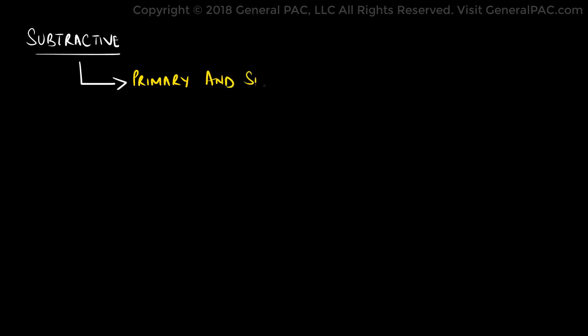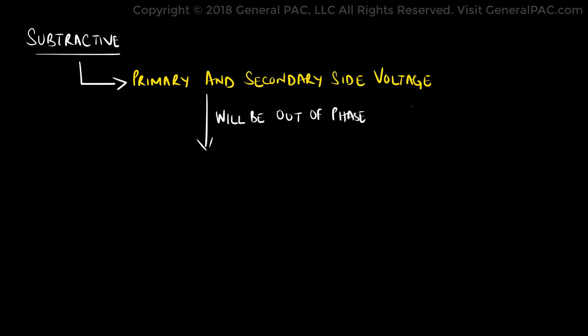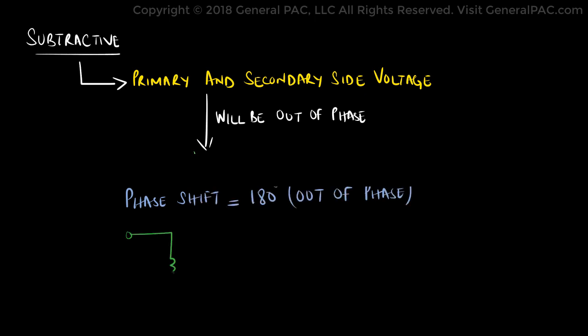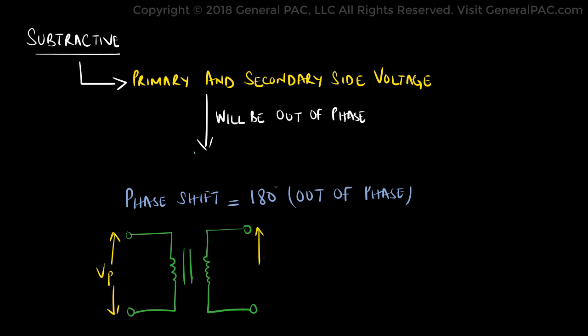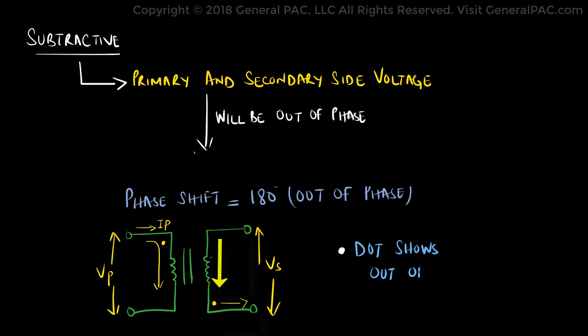On the other hand, if we consider subtractive polarity, then it means that the primary and the secondary voltage will be out of phase. In other words, they will have a phase shift of exactly 180 degrees. We can observe subtractive polarity by drawing a dot marking on the top end of the primary winding. However, for the secondary winding, the dot will be marked on the lower end instead. This is to show the out of phase characteristic.